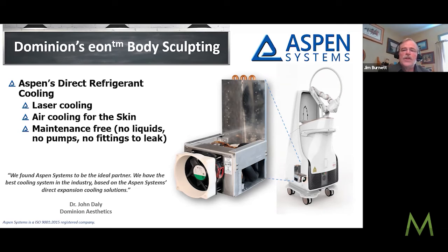A number of our customers have asked us to replace thermoelectrics in these applications, simply because the heat dissipated from the thermoelectric unit was driving up the temperature of the treatment room, causing discomfort for the patient and raising the ambient temperature to overcome the room's air conditioning. That in turn caused the thermoelectrics to fail because they couldn't keep up with the higher ambient temperature they themselves were producing. So it's really a three or four-fold effect of having the higher efficiency system in these units.